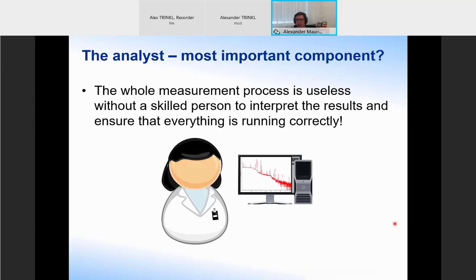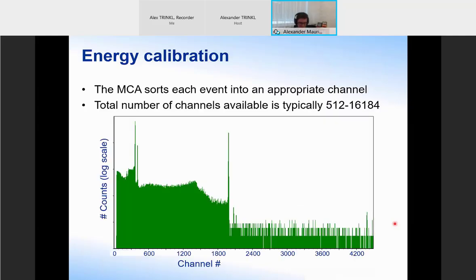I would like to introduce one more technical concept to you, and that is the concept of the energy calibration. So we talked a lot about how the multi-channel analyzer sorts each event into a channel in the spectrum, and there's a total number of channels available in the spectrum, which is usually between, let's say, 512 and 16,384 or 8,192. The reason why these are not round numbers is generally because these are powers of 2. So, of course, what the MCA is doing is sorting and making our spectrum into channels.